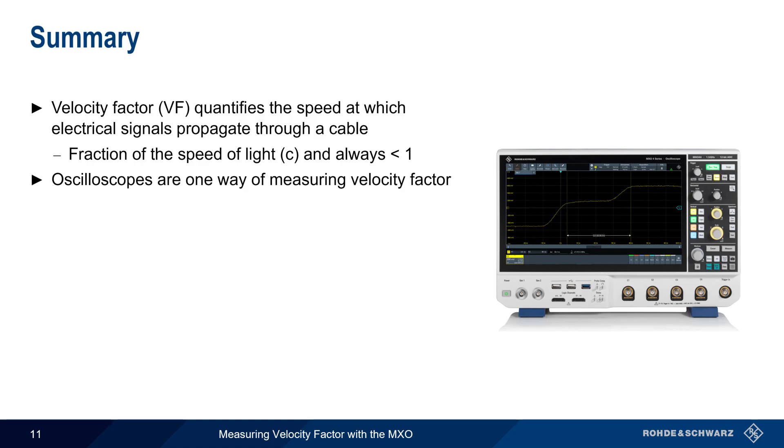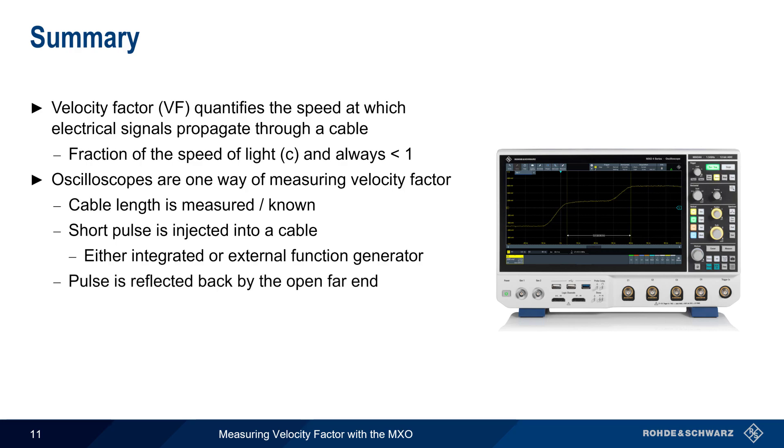The steps are as follows. First, the physical length of the cable must be known or measured. A short pulse with a fast rise time is then injected into the cable. This pulse can be created using the MXO's internal function generator, or by using an external generator. The end of the cable is left open so that this pulse is reflected back from the far end, and the round trip time between the transmitted and received pulse is measured by the MXO.